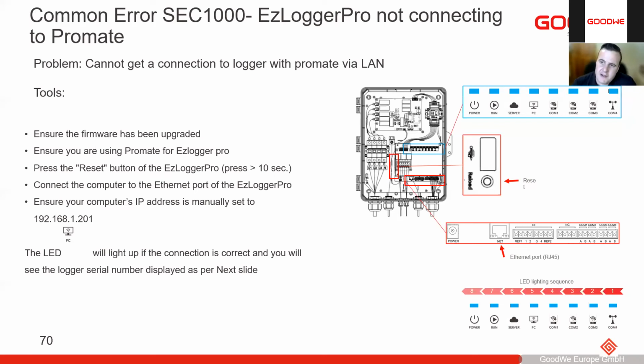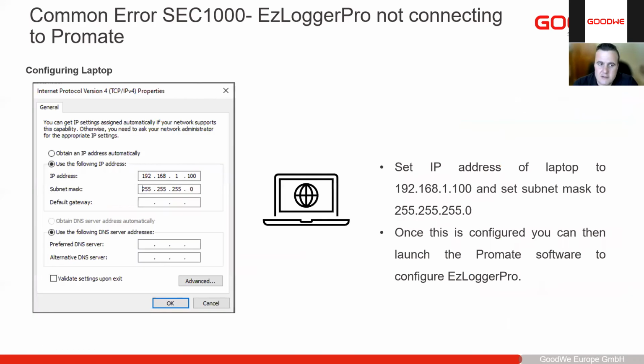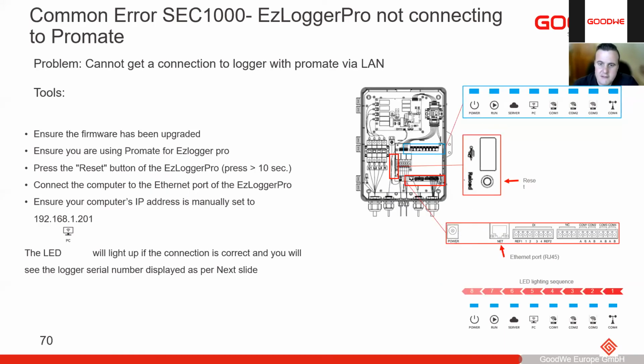Lastly, you need to make sure that our computer is set correctly, because you'll have to set a static IP address for the LAN of your computer as well. And that will just be your standard IPv4 protocols that you will set on this. So you can set 192.168.1 and then anything other than 200, and then the subnet mask, which is the standard subnet mask, and you don't require anything else. You can then just press OK, and then we should get successful communication.